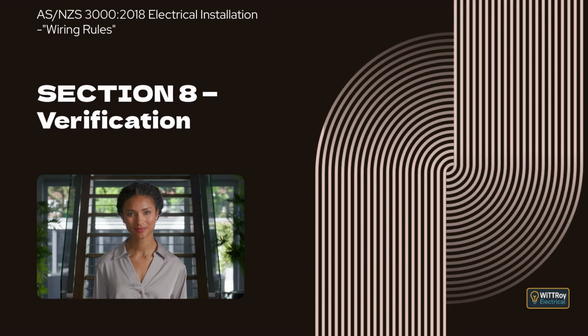Clause 8.3.10 Operation of RCDs. This clause explains that to verify correct installation, tests must be carried out on all RCDs. The function of the RCD must be verified either by operating the integral test device or by using suitable test equipment. The clause also explains that after an RCD has operated to disconnect the designated circuit, isolation of all switched poles must be verified. This can be done by voltage tests or by continuity checks after removing supply.